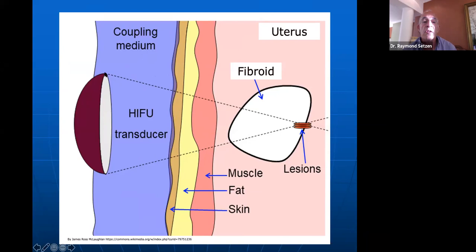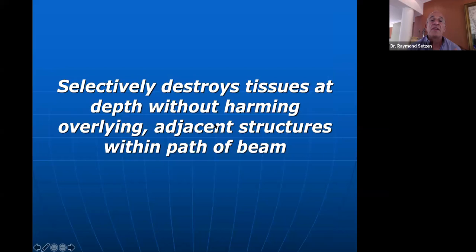So there's minimal damage to these structures in between the transducer and the fibroid. What happens with HIFU is that we selectively destroy tissue at depth without harming overlying tissues or adjacent structures within the path of the beam.